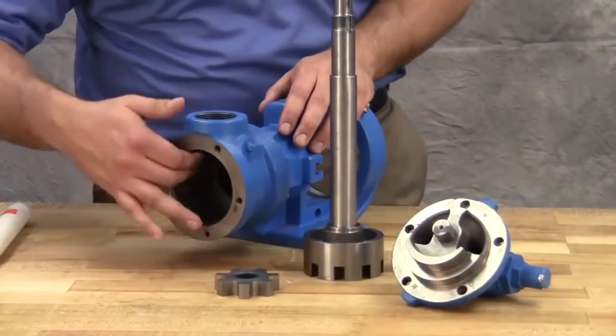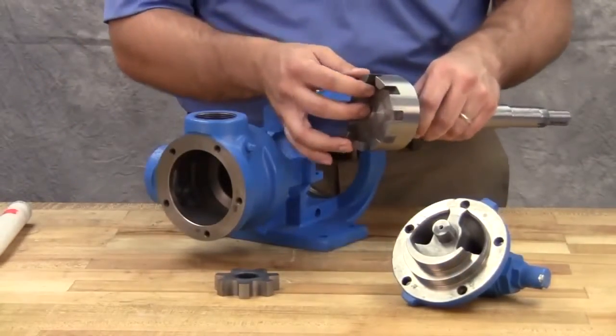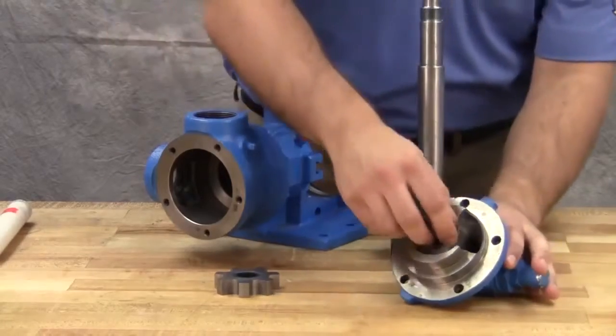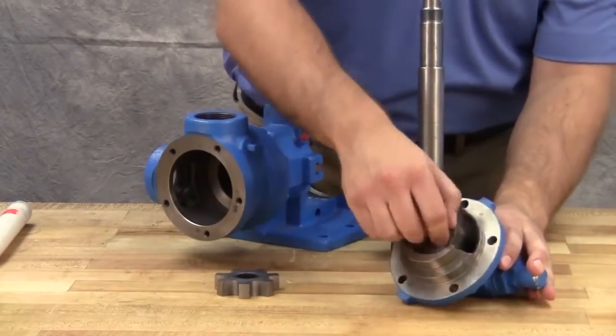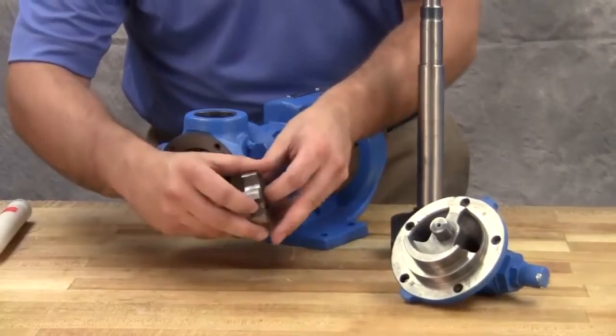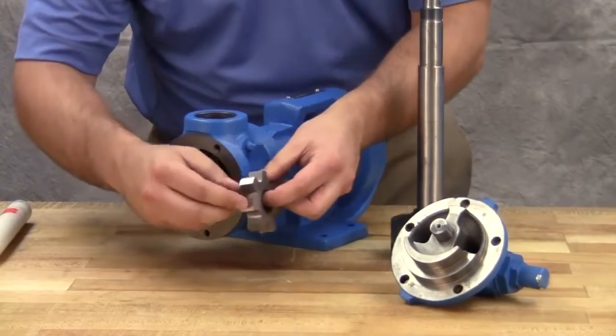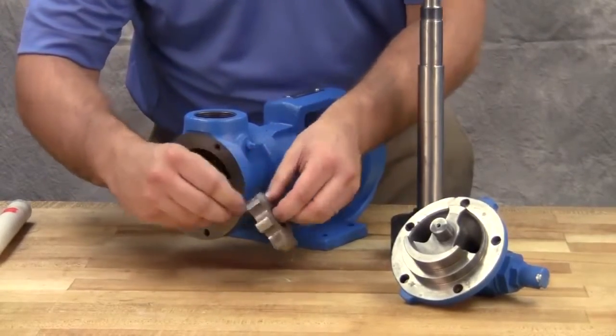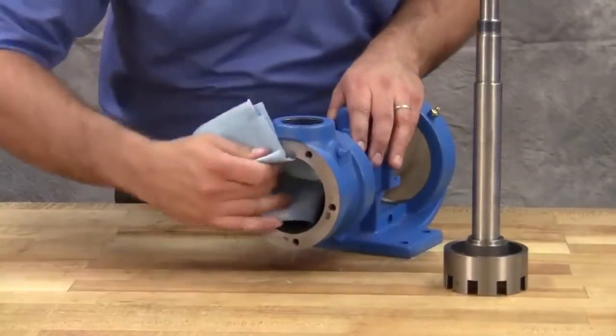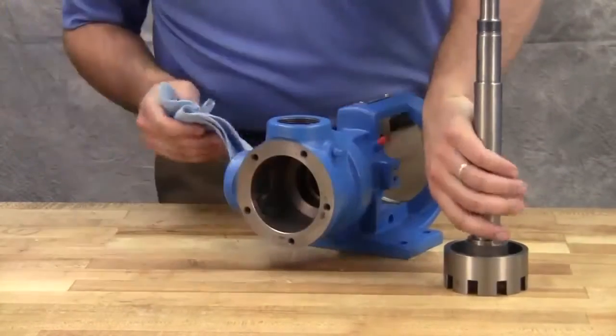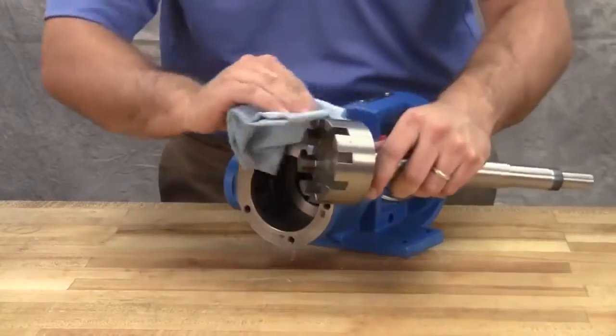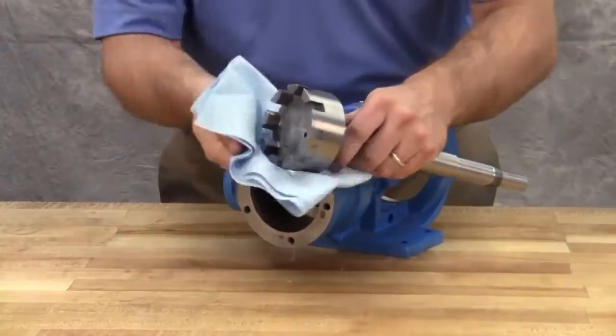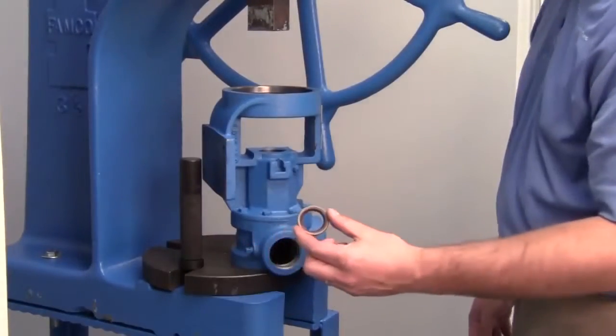Inspect the pump parts for wear, particularly the critical parts such as the idler pin, idler bushing, bracket bushing, idler gear, rotor, and casing. Check parts for nicks, burrs, and excessive wear and replace any worn components. Clean the rotor hub and casing bore. Make sure both are free of dirt and grit. Install the lip seal into the bracket.